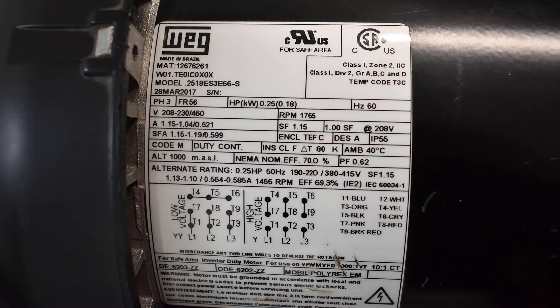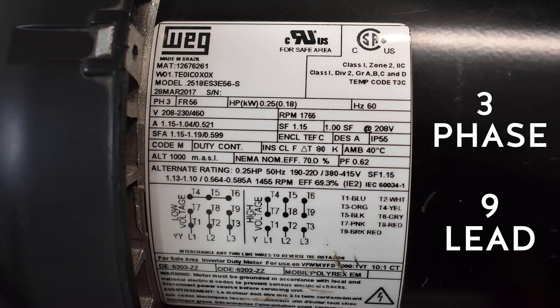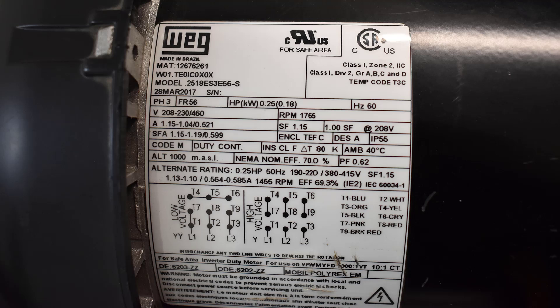What we're looking at here is the nameplate on a three-phase nine-lead motor. This is very important because it tells you the voltage on the motor, the amperage the motor will draw, and also how to connect the leads for high voltage — which would be 480 volts — or 230 volts, which would be low voltage.